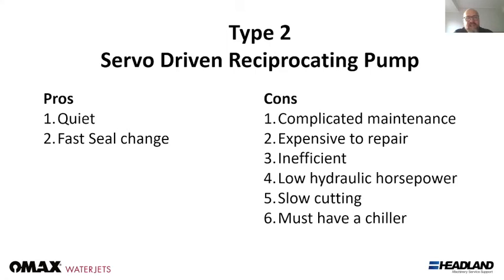Now, what are the pros and cons of that? One of the biggest positive features of the servo-driven pump is it's very, very quiet indeed. And it just sits there and purrs away in the corner. It sounds like a dishwasher, just sloshing a bit of water about. The way that they've been designed, they're quite fast just to change over a single seal. That's normally not what you do with a full maintenance though. Normally if you're doing maintenance, you need to replace more than just the seal. There's check valve components and cylinders and all this kind of stuff as well. So it is fast just to change one seal, but that's not normally what you're going to be doing.